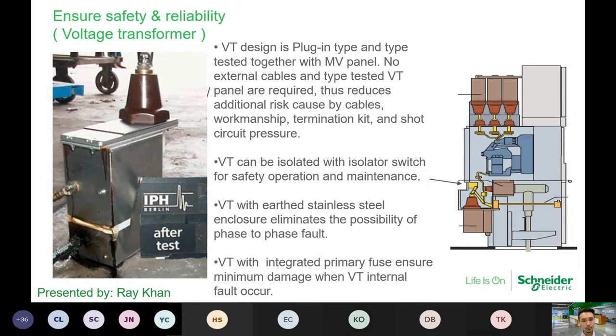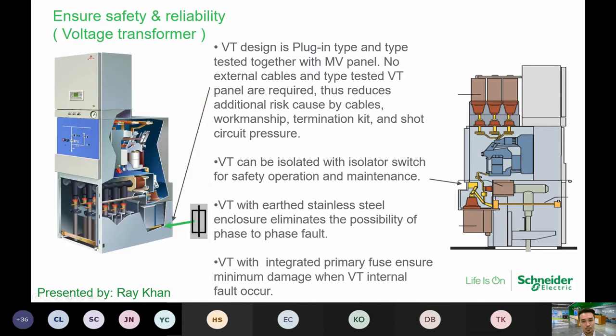All right. So I think one of the very common questions is, for the VTs with the integrated primary fuse, once it's damaged, do we change the whole VT? Well, I would say the answer is yes, because the fuse is actually located inside the VT itself. Once the fuse blows, pretty much the root cause a lot of times comes from the winding, and the winding actually resides in the VT, right? So a lot of times when the fuse blows, it means that the VT is actually having an issue as well. So that is why our recommendation is to have the box changed as well. Okay.